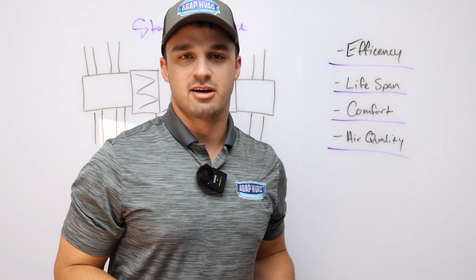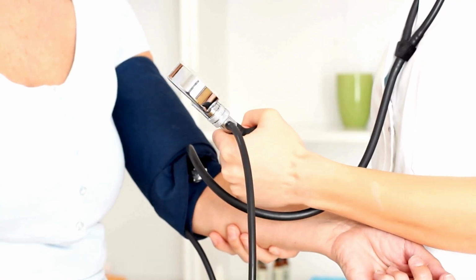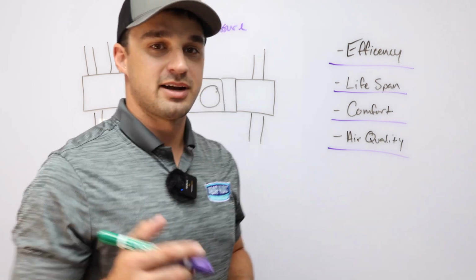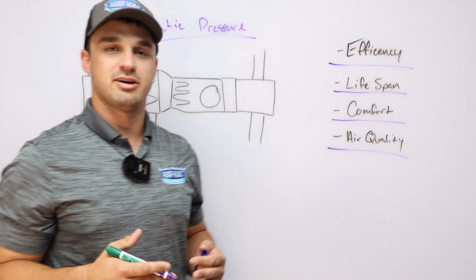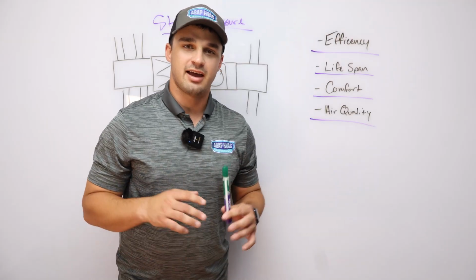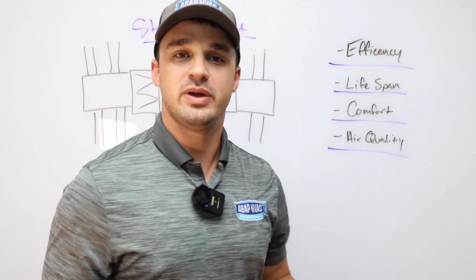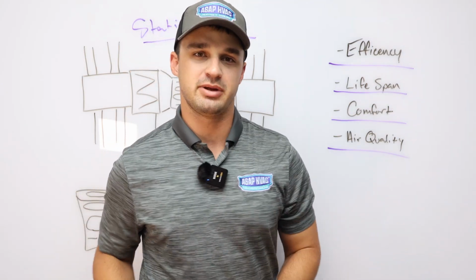Every time you go to the doctor's office, what do they do? They check your blood pressure, right? And they say, blood pressure is the silent killer. And that's true. Something else that's true is static pressure is the silent killer of your AC system. And it's something that you should check, just like your blood pressure, every time you have a technician visit your house. Static pressure is a measurement that we can take as AC technicians that'll tell us if your airflow is where it should be or not.